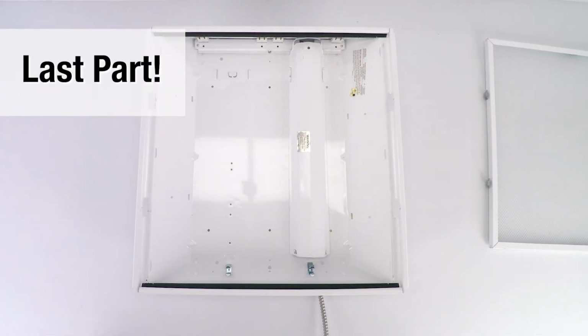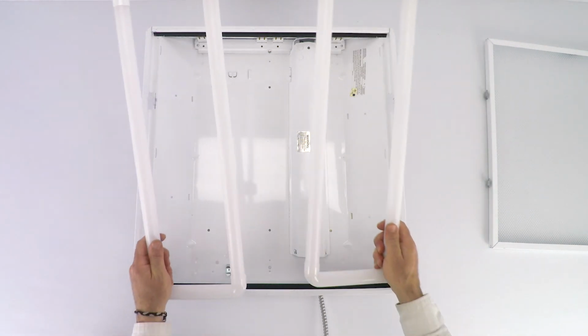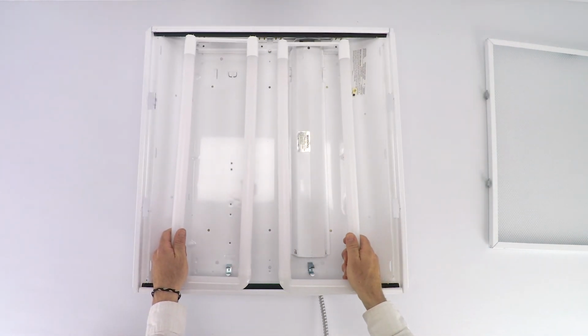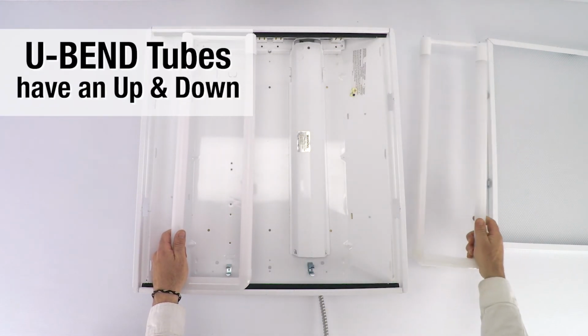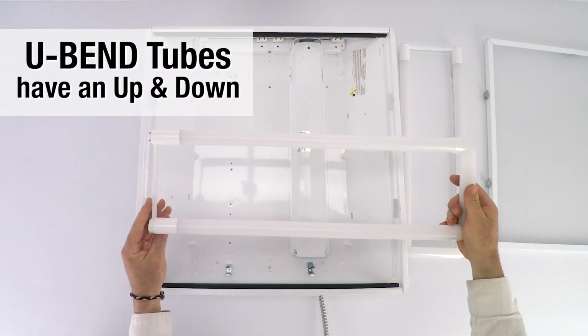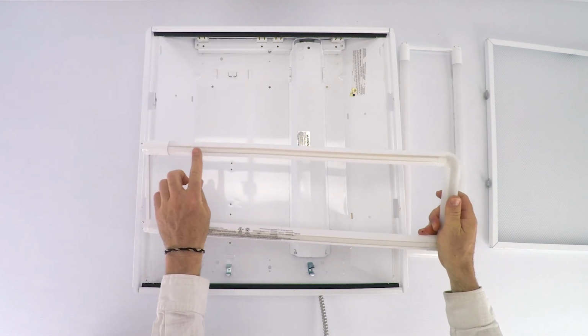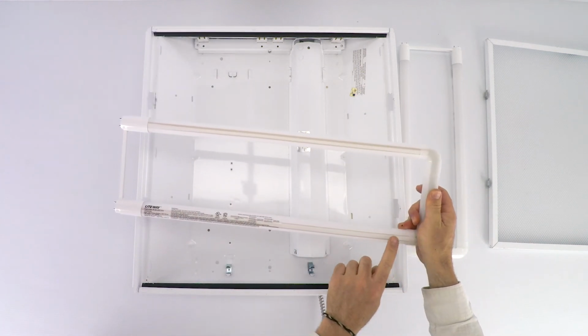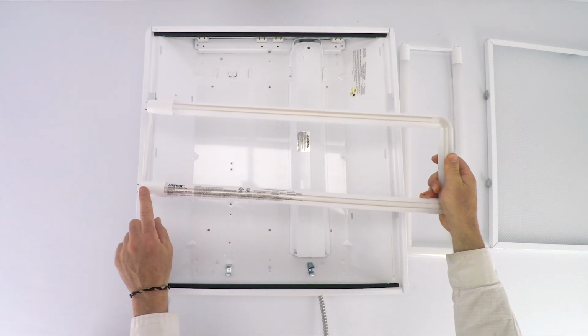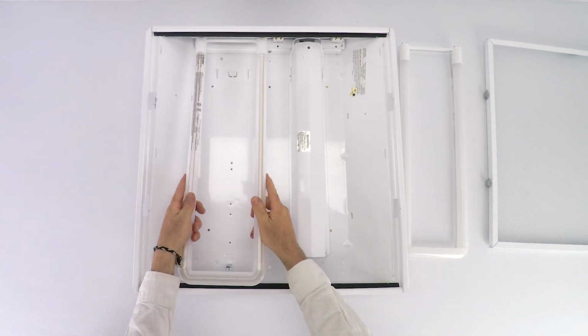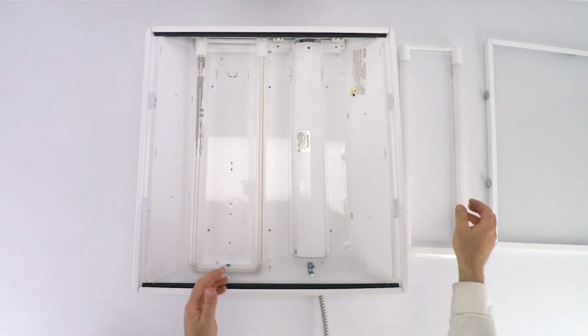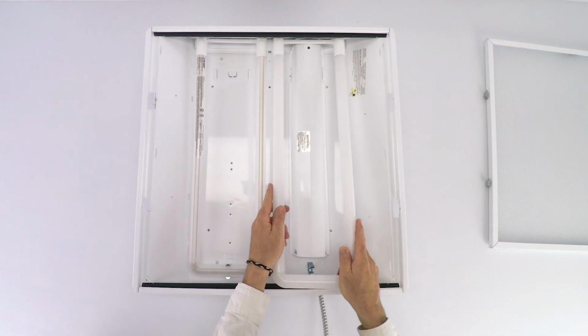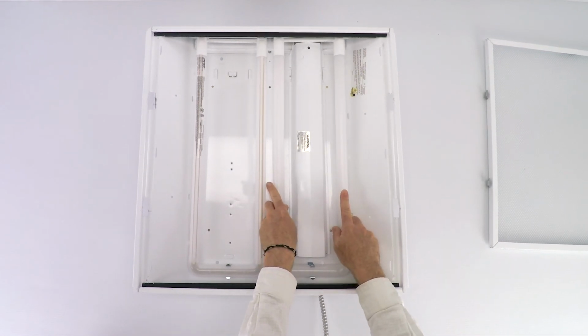All right, this is the last part to the conversion, and probably the easiest, but you got to pay a little attention. So you're going to put our U-bend tubes in the fixture now, and the U-bend tubes have an up and a down. Inside the U-bend tube is a little piece of tape with a whole bunch of LEDs on it that run down the inside of the tube on one side. So if you put your tube in upside down, all the light's going to be facing up into the reflector. Not very efficient. And you'll see it right away, and it's not a big deal.